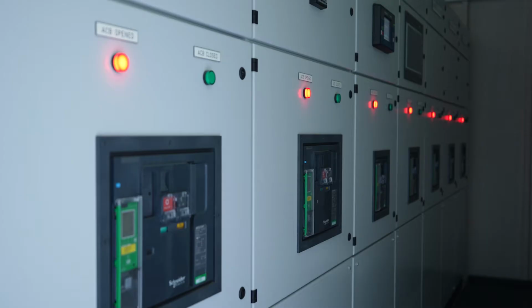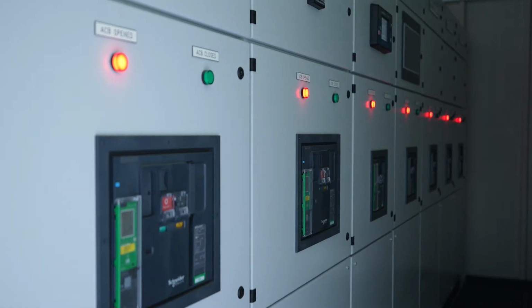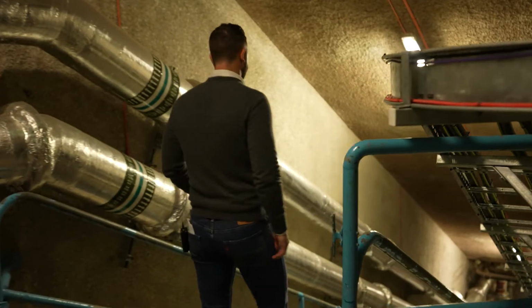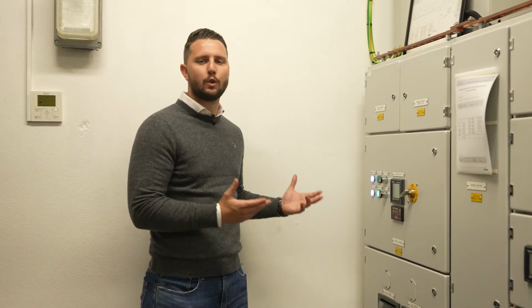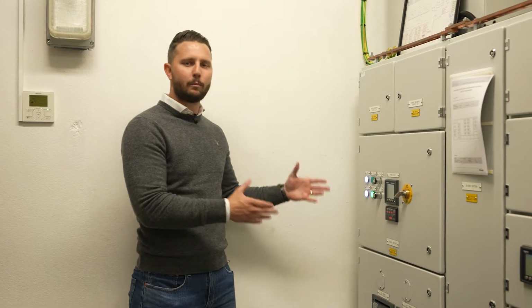I'll show you what an LV1 or LV2 looks like and how that feeds into our UPSs, or uninterrupted power supplies. We're now 30 meters underground in UPS 14, and the power has now been converted into low voltage power, or 400 volts. This is now usable power, distributed from here to our customer's rack.